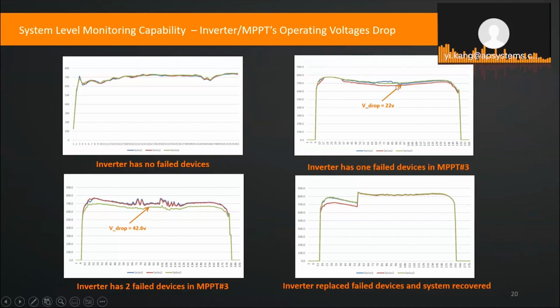So this is real data. One day, we found a drop from one of the MPPT monitors, and the drop was about 20 volts. It's pretty much equal to the maximum power voltage of one panel. After a while, we learned that another device in the same string was failing, so the drop expanded to 45 volts, which means two devices had failed. Then the customer sent a crew to the system to replace those two devices. Immediately the system came back. So by this case, we learned that just monitoring the voltage at your string inverter makes it easy to know whether your RSD devices are functioning or not.